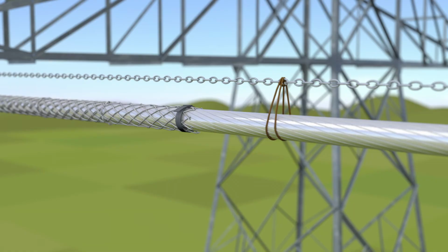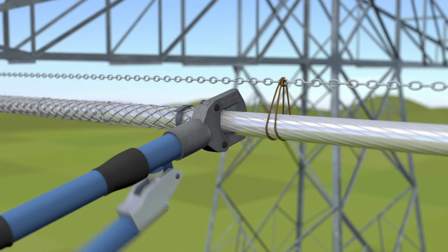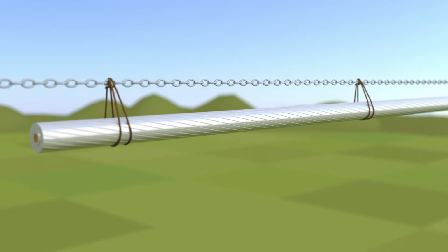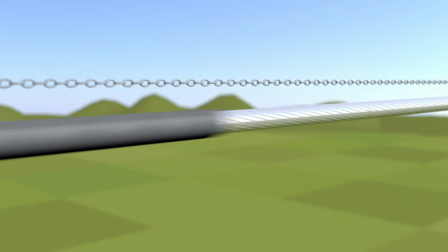Once the conductor has been pulled up and clamped in the tower, we can remove the pulling eye by cutting the conductor. The end of the conductor is now free to work with for fitting the dead end. We slide the dead end inner and outer sleeves over the free end of the conductor.